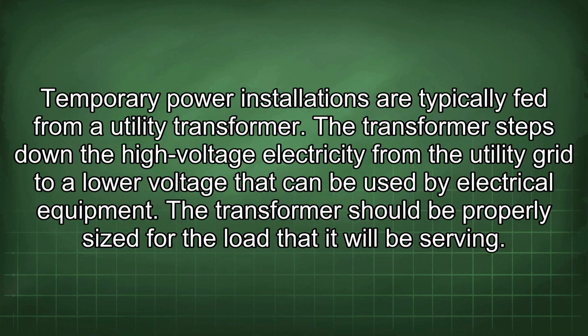Temporary power installations are typically fed from a utility transformer. The transformer steps down the high voltage electricity from the utility grid to a low voltage that can be used by electrical equipment. The transformer should be properly sized for the load that it will be serving.